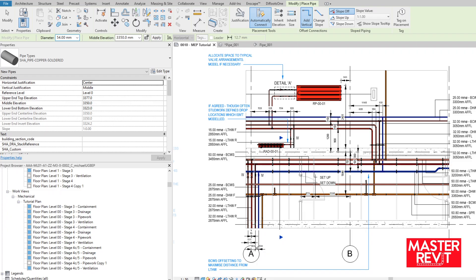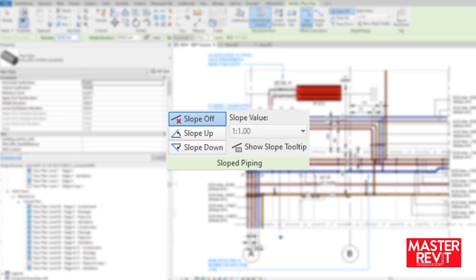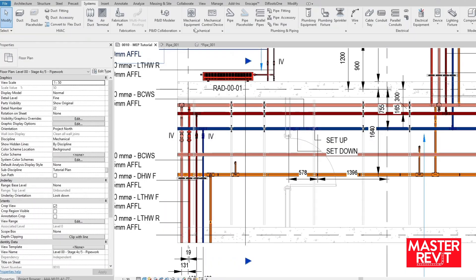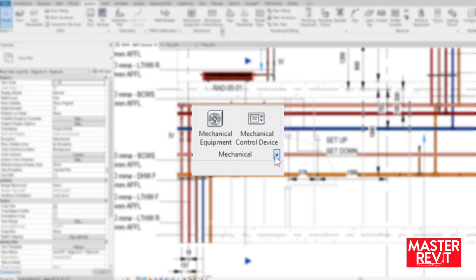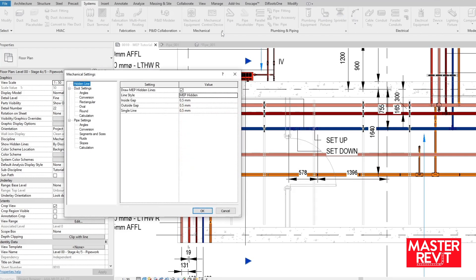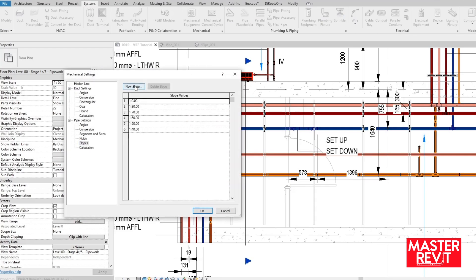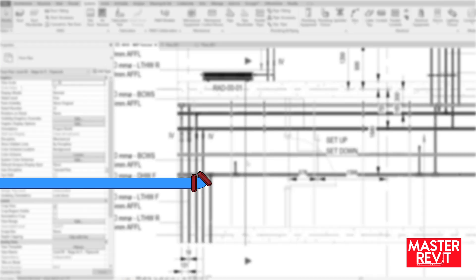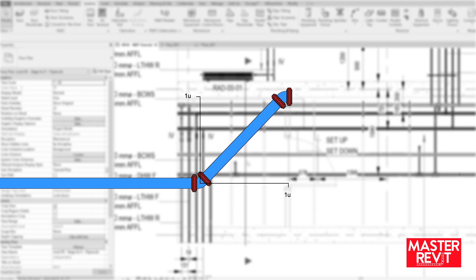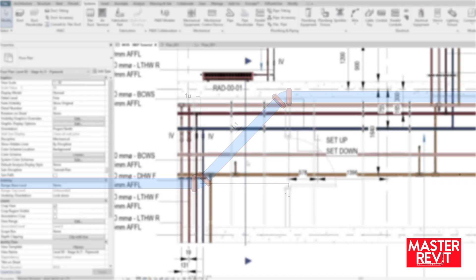So, an alternative method is to utilize the slope function. It does require a quick update to Revit settings. Go to the system tab at the top and click the little arrow at the bottom of the mechanical section. Once you're in the settings go to slopes, new slope and create a value of 1 to 1, which is essentially one unit of travel along the horizontal axis for every one unit of travel along the vertical axis, resulting in a 45 degree pipe.